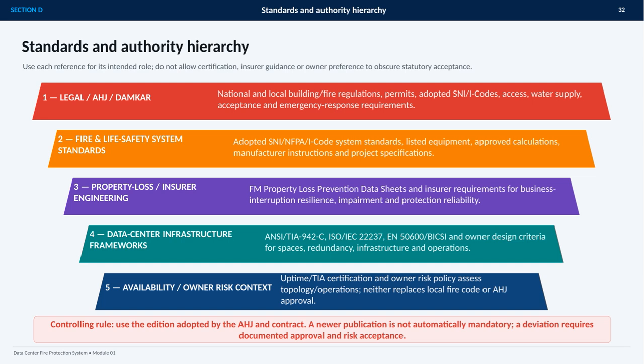operations. Certification and owner risk policies are valuable for assessing topology and availability, but they do not replace local fire code or AHJ approval. The practical rule is to use the edition adopted by the AHJ and written into the contract. A newer publication is not automatically mandatory, and any deviation needs documented approval and explicit risk acceptance.